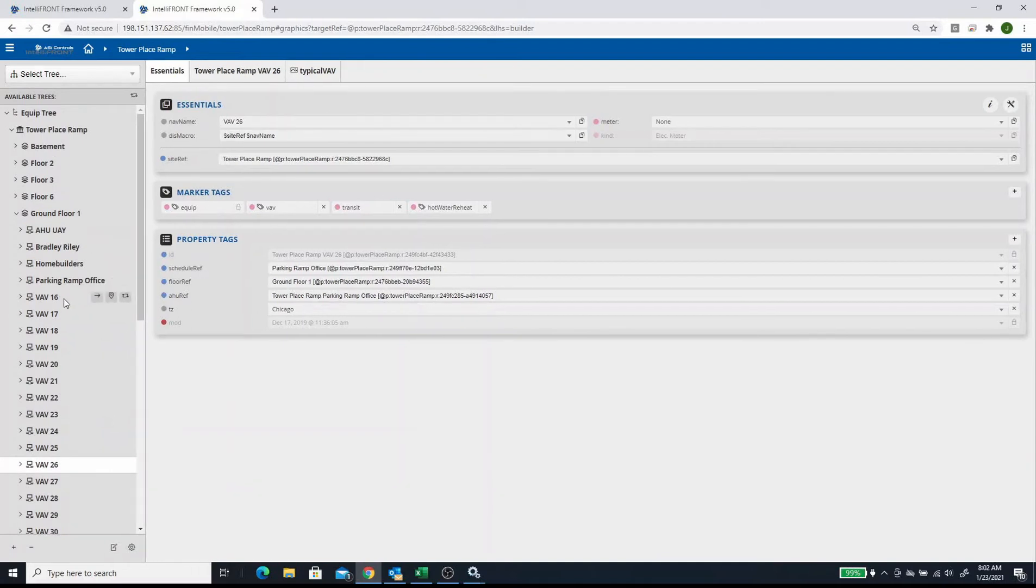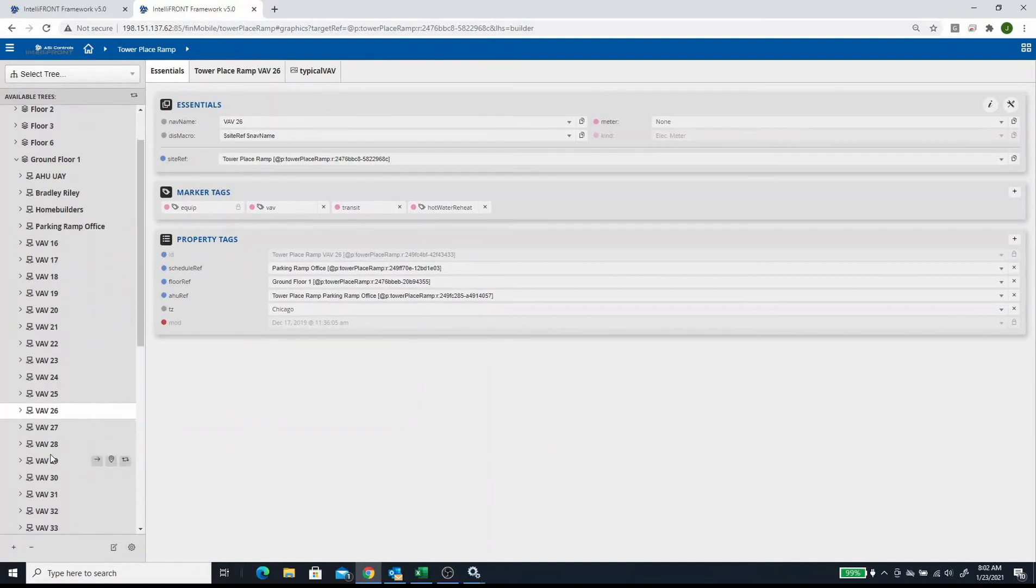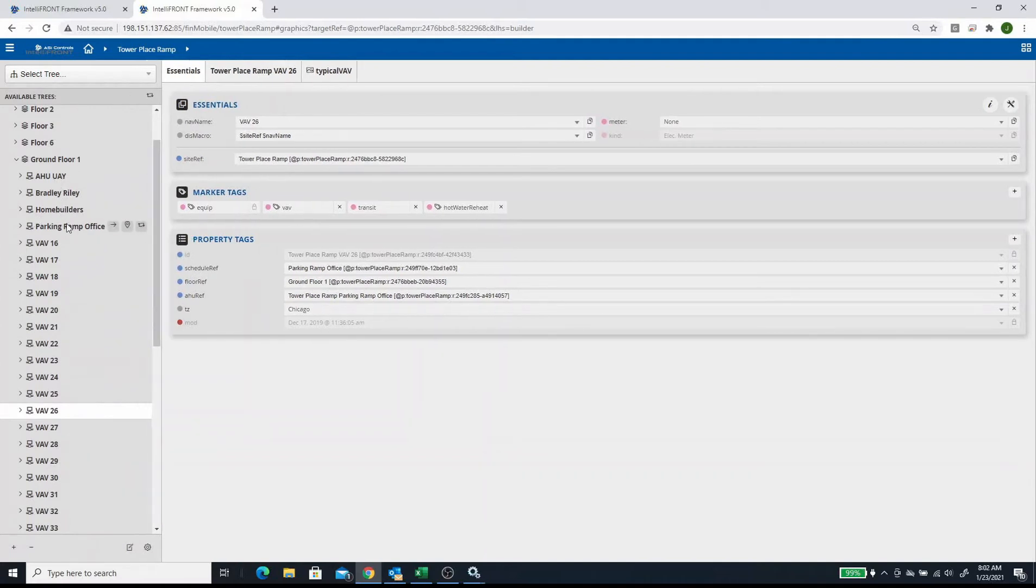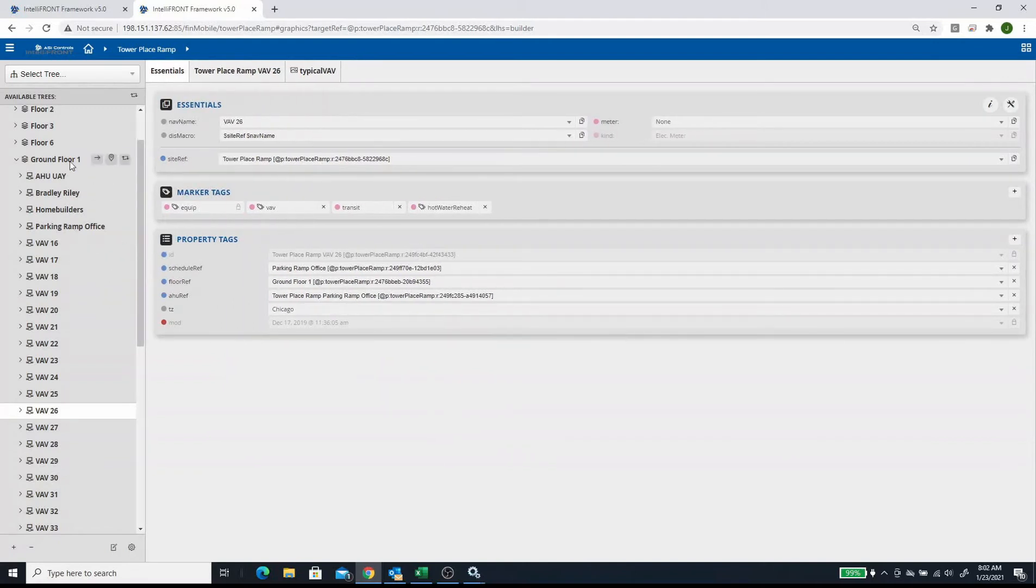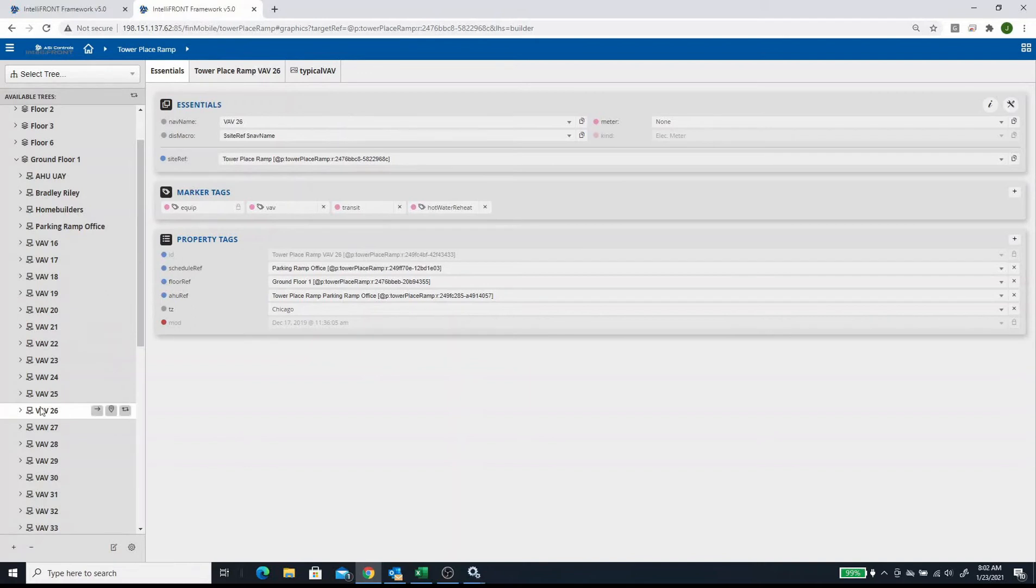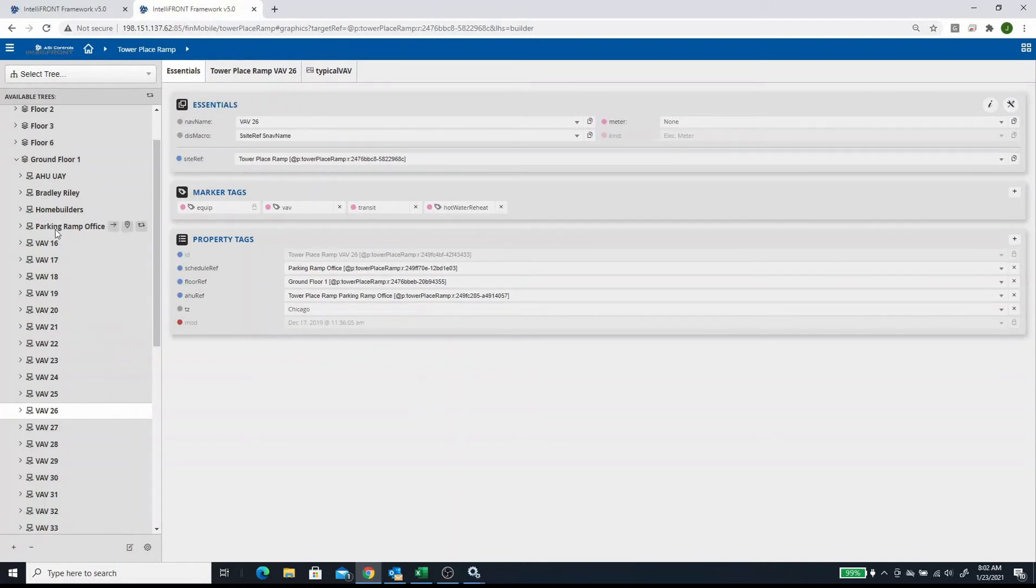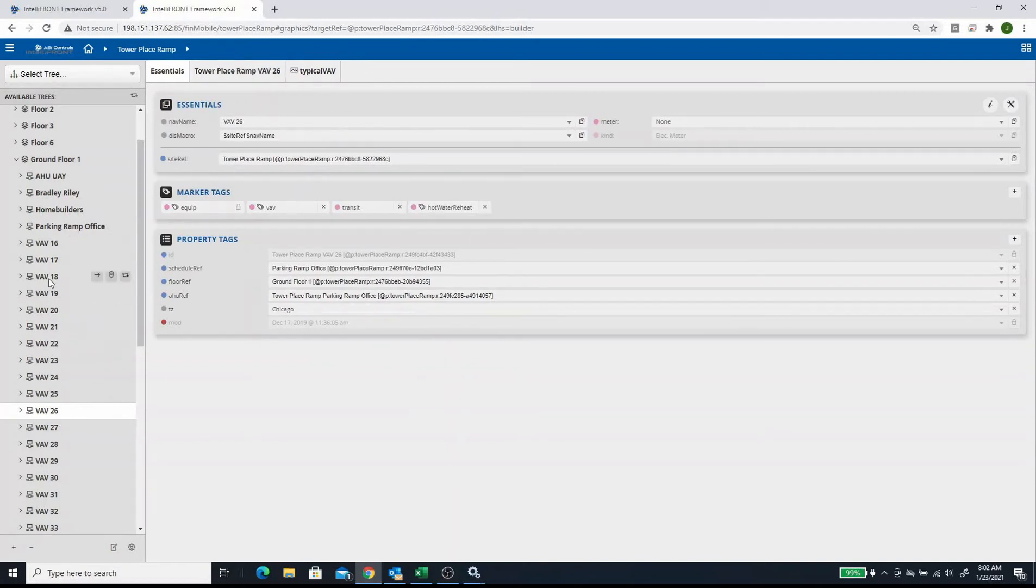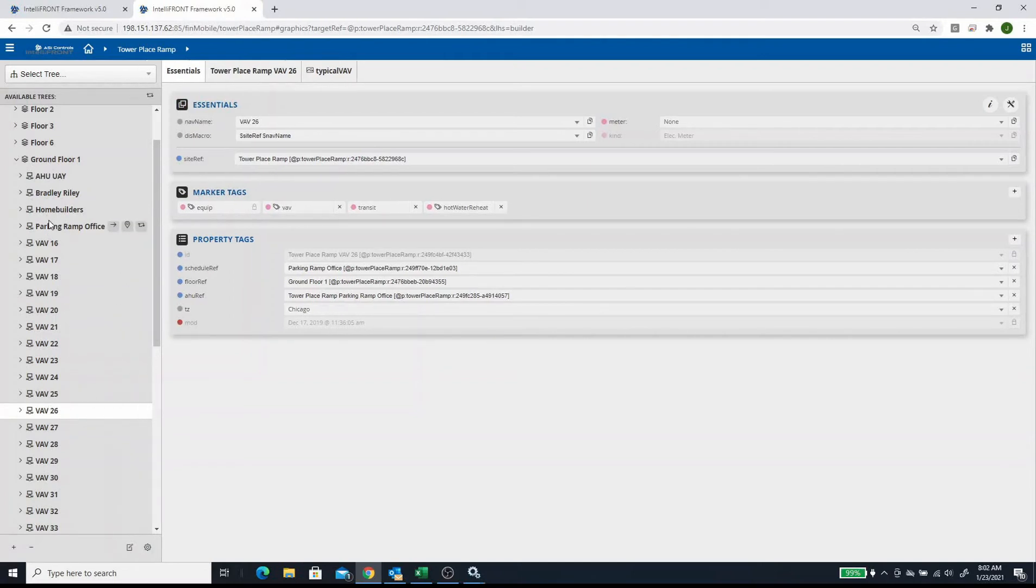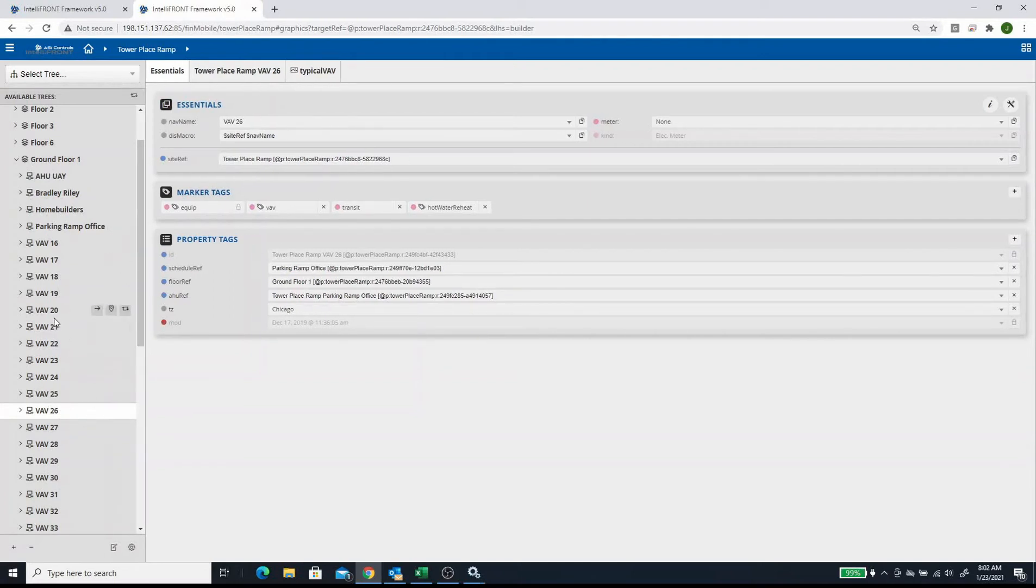But if I would have taken VAV 26 through 28 and threw it underneath this air handler for Parking Ramp Office, then when you go to build your ground floor graphic, it's not going to reference those VAVs because they're disassociated. You want all your VAVs underneath the ground floor, and then you make these VAVs reference your air handler.